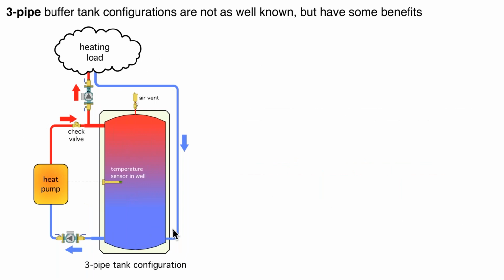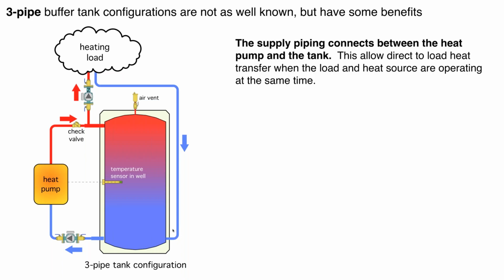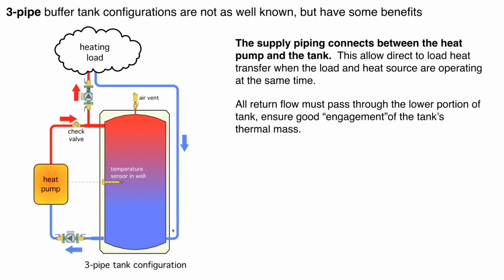So 4-pipe, 2-pipe, now let's average them out. Let's go to a 3-pipe. We're still getting our direct to load transfer, so we're retaining that benefit. All the return flow has to come back through the tank, through the lower portion of the tank. So we are fully engaging thermal mass. There's always going to be some flow going through the tank, okay? Which, again, I gave you that scenario with the 2-pipe buffer.